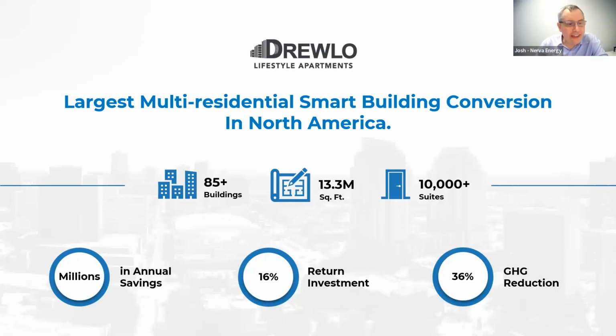Yeah, absolutely. This has bothered me for many years. There are a lot of older multi-res buildings across the country built with central exhaust systems. There are two ways to build multi-res: with in-suite exhaust, meaning the range, dryer, and bathroom exhaust vent directly out through the sidewall for every suite as an independent system, or with exhaust riser stacks that pull exhaust air from every suite up to the roof and exhaust it out there. I can't tell you how many hundreds, thousands of buildings have these central exhaust systems.